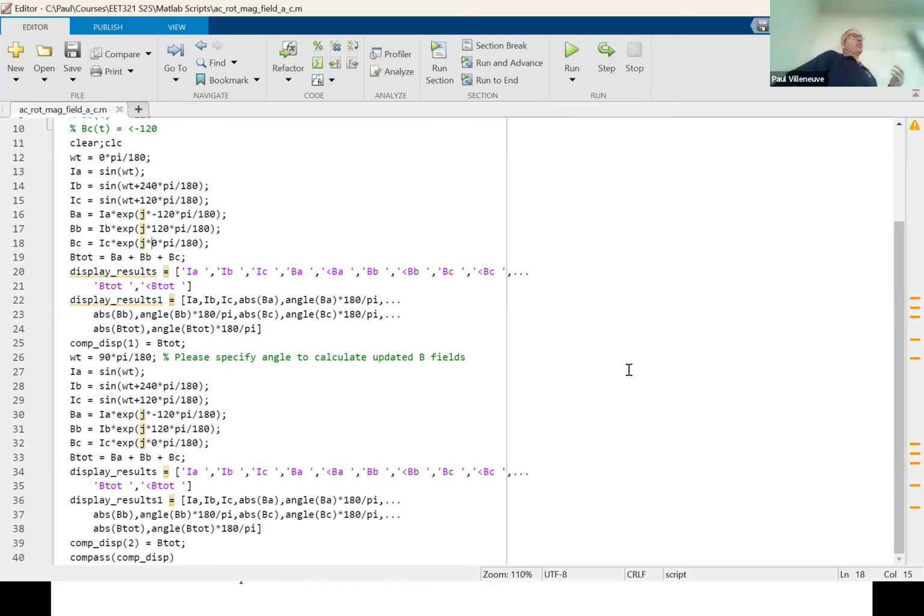If it runs in the right direction, then you're done. If it's running in the wrong direction, then you swap it out. Do you remember when we started talking about three-phase towards the beginning of the semester? I said most of the time you don't even care how the machine is wired. Here's why. If it's running in the wrong direction, you just swap them around. It doesn't hurt the motor. It doesn't hurt the electrical supply. It doesn't matter any of that. As long as you're connecting it three-phase, works beautifully. No issues, no concerns. Okay.